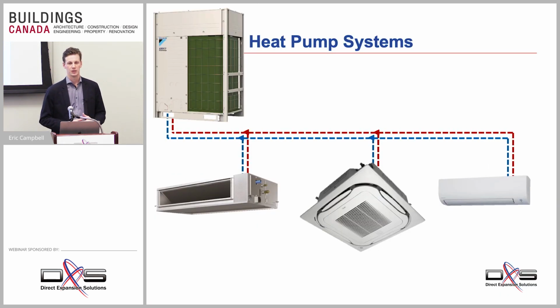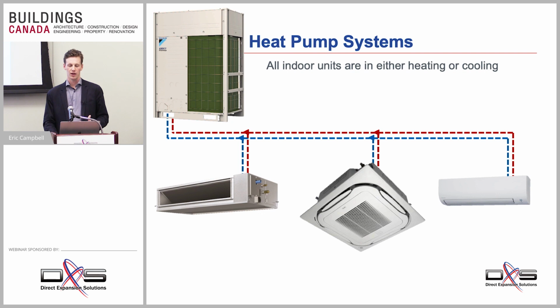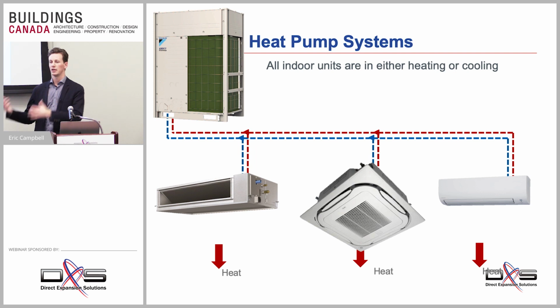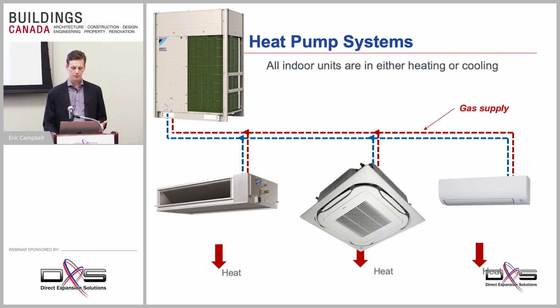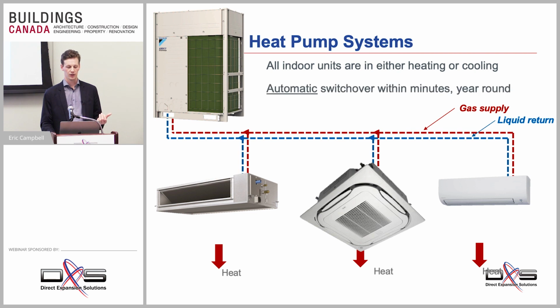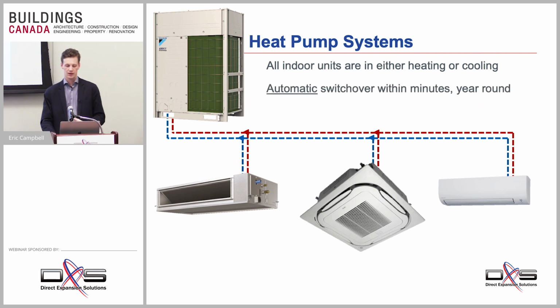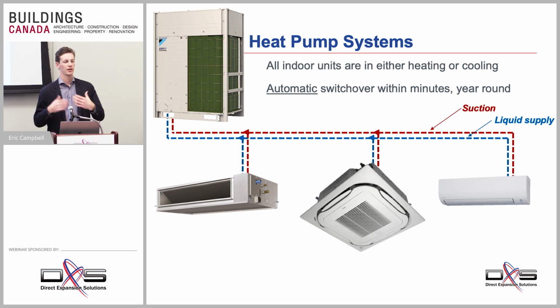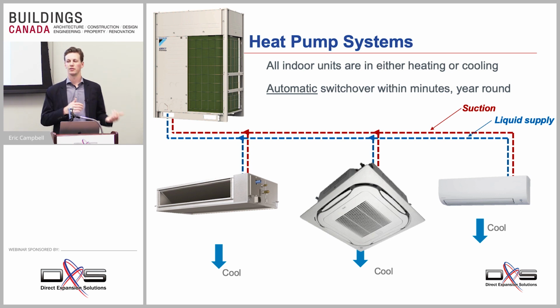There are two fundamental types. They're both heat pumps, but we talk about changeover systems and heat recovery, or simultaneous heating and cooling, systems. The first heat pump system is the simplest VRF, and there you have all your indoor units connected to one outdoor unit in one mode of operation. So they all have to be in heating or they all have to be in cooling. We're able to do a changeover that switches between heating and cooling fairly quickly. It only takes a few minutes. But again, the key thing to remember is that it needs to switch back and forth, and if you've got one zone that needs cooling and one that needs heating, they're not both going to be satisfied simultaneously. The system will have to switch back and forth.